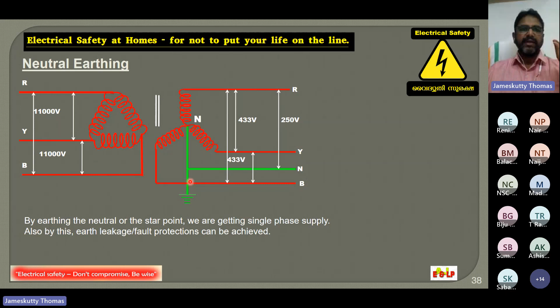So here, by creating the neutral point, we are mainly getting 2 benefits. First, we are getting single phase supply. We can get a single phase connection between the neutral and one of the three phases, thereby we can operate our single phase loads. It means we can get 250 volt or 230 volt. That is one of the benefits of earthing this neutral. Additionally, by this neutral, we can get earth fault or leakage protections. We can understand this through the operation of an RCCB at a later stage.